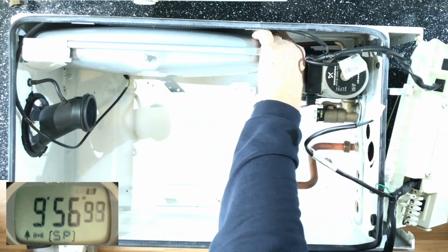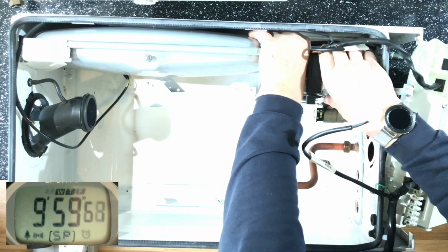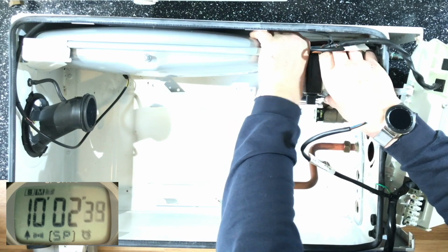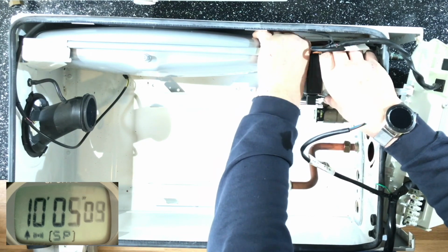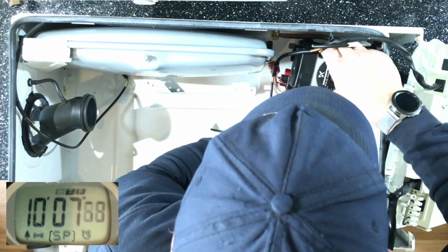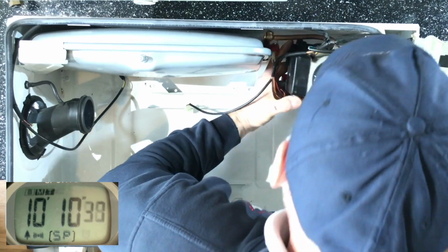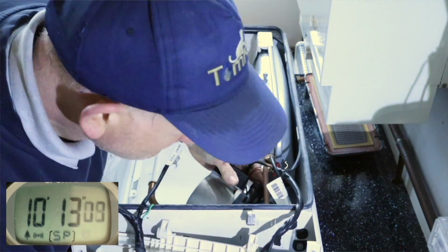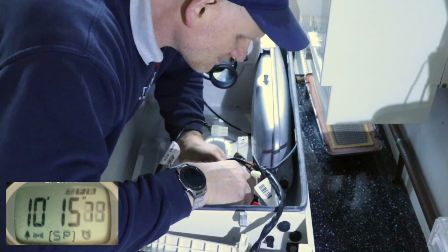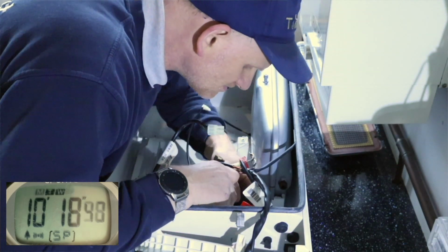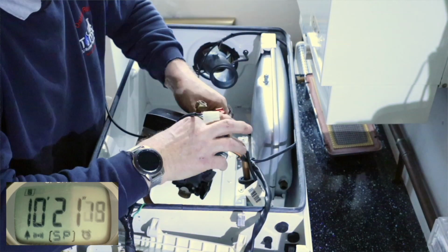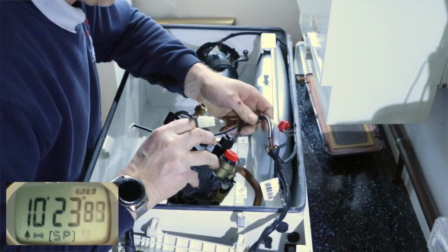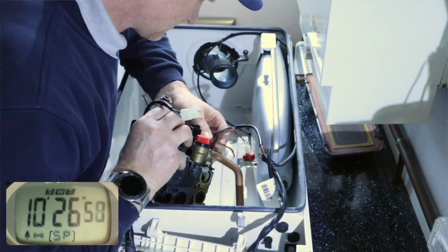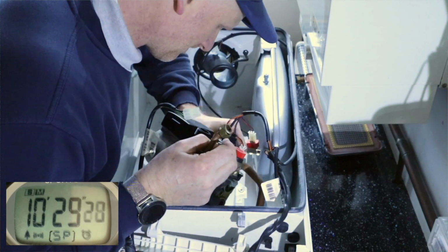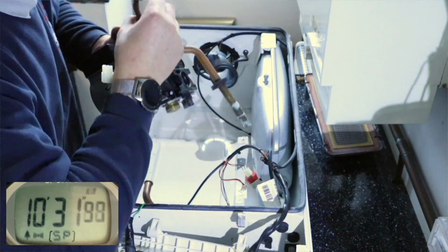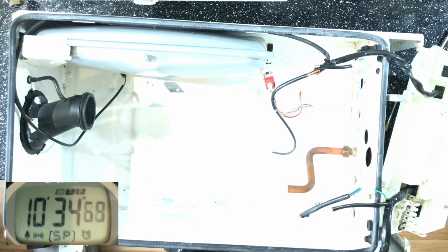Now one thing to look out for when you're changing the expansion vessels on these boilers, the actual connection off the pump is different on the newer versions than it is on the older ones. So as you can see on this one, it's still a copper pipe going up to feed the expansion vessel, but on this one it comes off the side of the pump, where the newer ones come off the back of the pump. So you've just got to watch out that you make sure you get the right expansion vessel. But the expansion vessels are the same. They're the same for the 24, 13, 35 kilowatts. There's no difference with these expansion vessels.